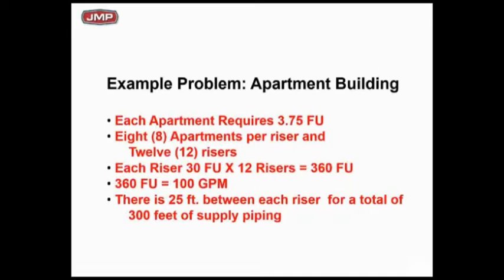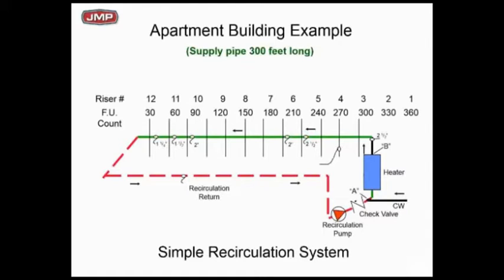Here we go with a typical fixture unit count for sizing pipe and coming up with demand, flow, and GPM. Note the bottom statement: we're going to have 12 risers, 25 feet apart. The total supply pipe length in the building is going to be 300 feet. Here's a little picture of this apartment with one water heater shown in blue and the green is the domestic hot water supply pipe, with each takeoff 25 feet apart.